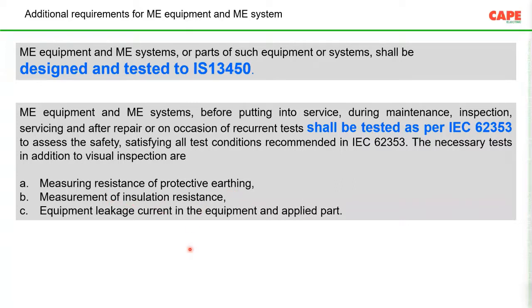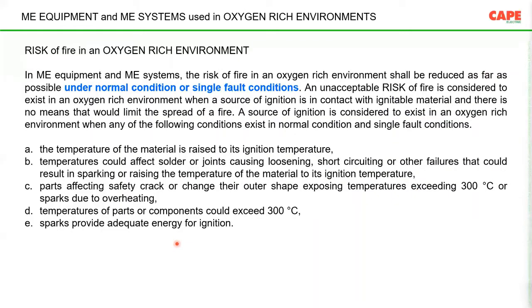Measuring insulation resistance is required. Then the equipment leakage current, to the equipment and the applied part. These 3 measurements are mandatory for every biomedical equipment or ME and ME system, once you connect or reconnect it into your system.